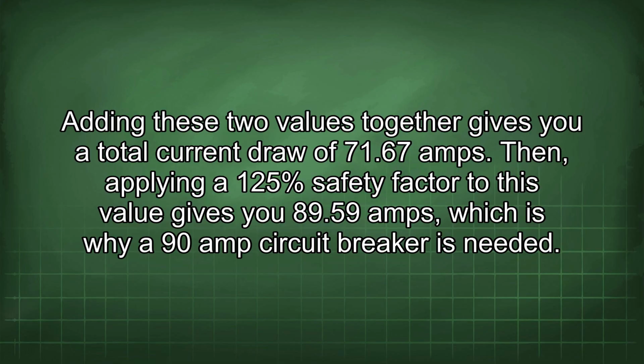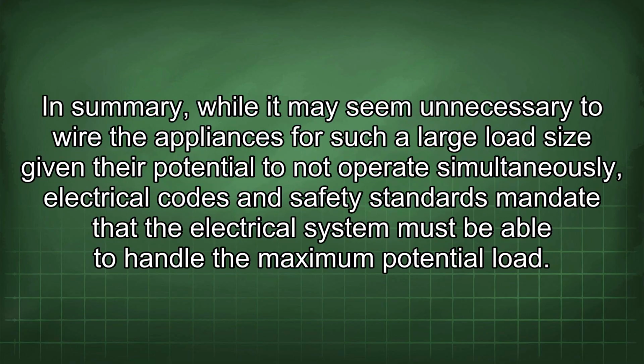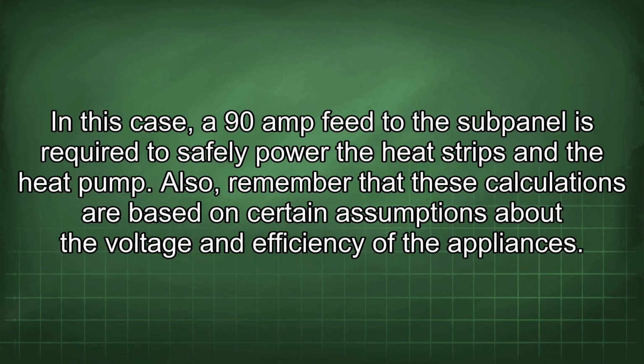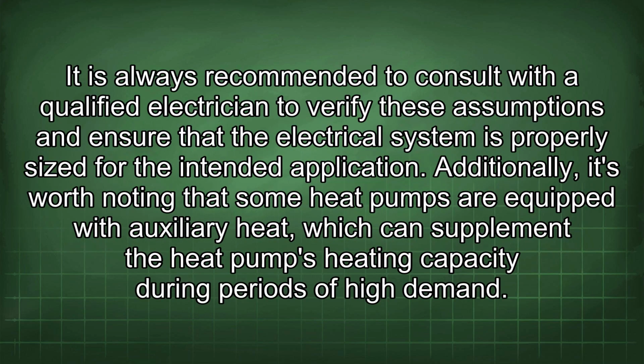In summary, while it may seem unnecessary to wire the appliances for such a large load size given the potential to not operate simultaneously, electrical codes and safety standards mandate that the electrical system must be able to handle the maximum potential load. In this case, a 90 amp feed to the subpanel is required to safely power the heat strips and the heat pump. Also, remember that these calculations are based on certain assumptions about the voltage and efficiency of the appliances. It is always recommended to consult with a qualified electrician to verify these assumptions and ensure that the electrical system is properly sized for the intended application.